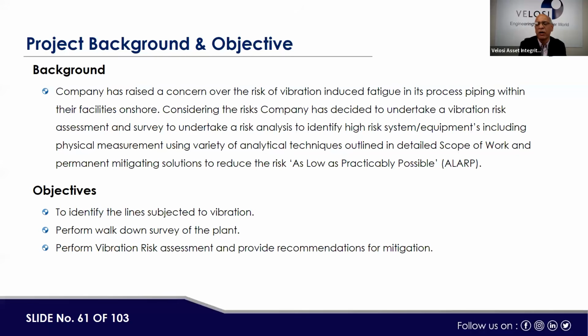See, when we are measuring the vibration at the plant, we will be able to see whether the associated upstream equipment, like a pump or compressor, is causing the vibration, or whether that location is downstream of a control valve, or at a flashing point or pressure reduction station, or is vibrating due to the absence of proper supporting. So as we go in the field for vibration measurement and site surveys, we will be able to know that. When we are doing root cause analysis or surveys in the field, we will be able to know the actual cause, and then the required corrective action can be taken.